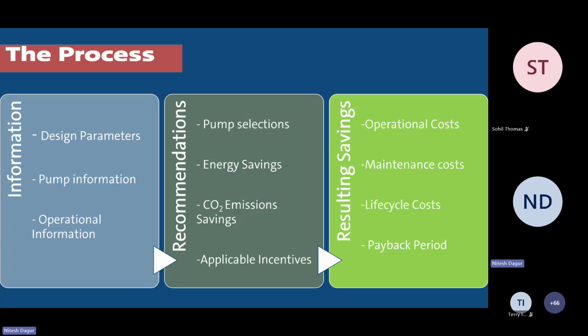Based on that, there's a payback period that is indicated in the report that I will be showing you in a minute. I want to highlight here that when we do the Booster Check and make the recommendations, a lot of the time this is a resizing of the pump. We do not encourage like-to-like solutions for booster pumps, especially because a lot of the pumps are oversized in the field. He will be talking about that as well, so you will see that happen.